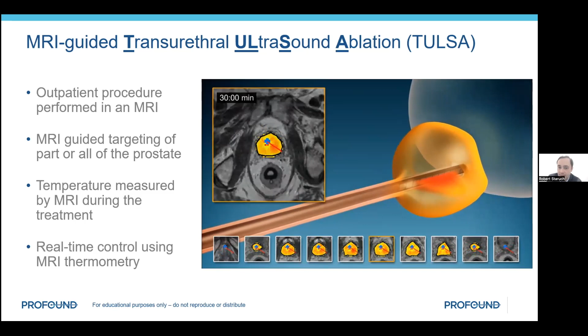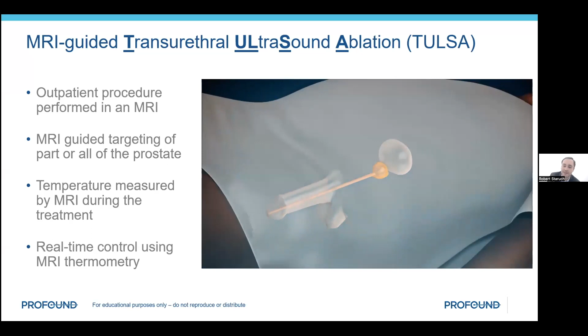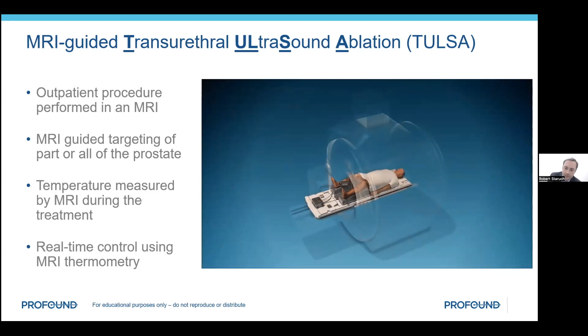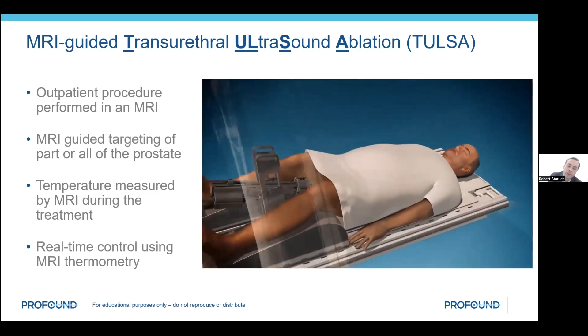While that's happening, the software of the Tulsa Pro system is using that temperature information to, in real time, make decisions about the ultrasound power that should be used for each of the transducer elements, the frequency that each of those ultrasound elements should use, which controls the ablation depth, and how fast to rotate the device. And that time of exposure related to the rotation of the device, and then the amount of ultrasound energy that's emitted is then causing different rates of temperature rise, which allows the physician to control exactly what temperatures they want within the prostate. The software is tuned to achieve a thermal coagulative temperature of 55 degrees Celsius at the target boundary that the physician has prescribed, and the heating extends from that point inwards all the way to the device. So you have temperatures between 55 and 86 degrees throughout the prostate between the device and the target boundary.